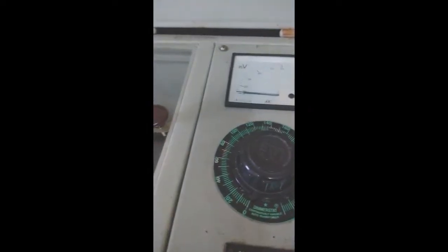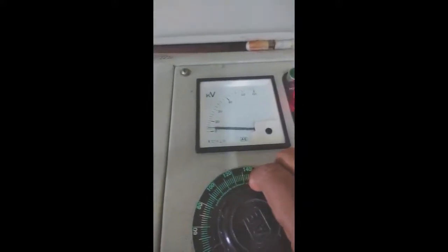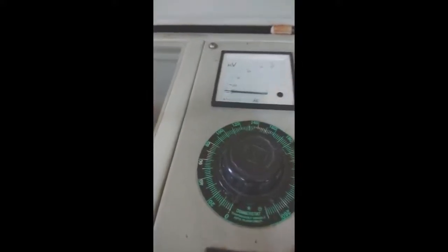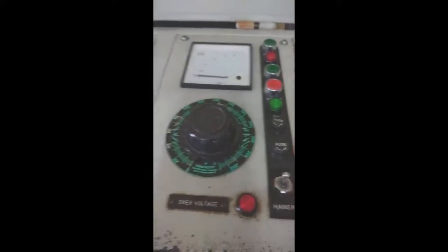repeating this experiment for my second reading. I have switched it on, that is HT on, and gradually I am increasing the supply voltage in kV. This is increasing voltage. This is increasing voltage. This has tripped. So this is the memory, and this is our second reading, that is also 52 kV. Now I will turn off this variac and switch off this instrument. So you can perform this experiment.